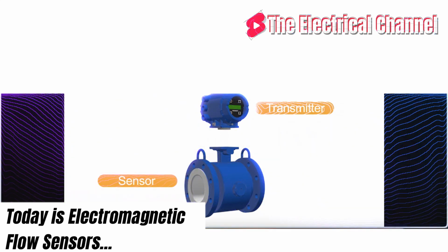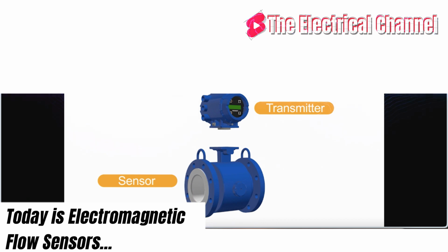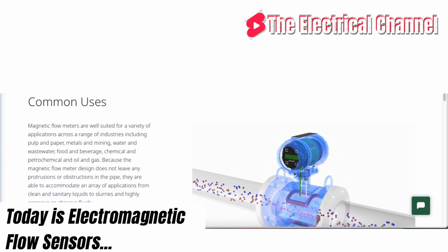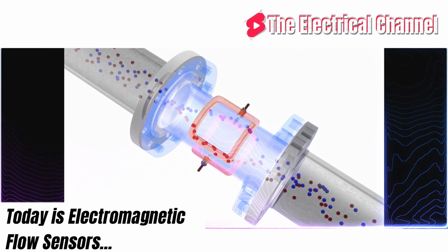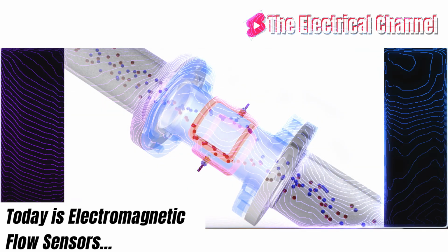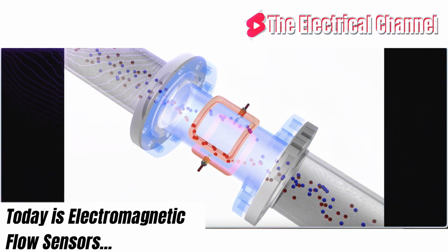This voltage, tapped by two measuring electrodes, is directly proportional to the velocity of flow, and thus to the flow volume. The magnetic field is generated by a pulsed direct current with alternating polarity. This ensures a stable zero point and makes the flow measurement suitable for multiphase or inhomogeneous liquids, as well as low conductivity.